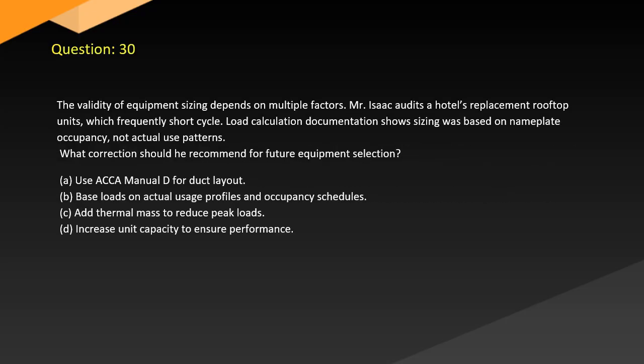Question 30. The validity of equipment sizing depends on multiple factors. Mr. Isaac audits a hotel's replacement rooftop unit, which frequently short cycles. Load calculation documentation shows sizing was based on nameplate occupancy, not actual use patterns. What corrections should he recommend for future equipment selection? A. Use ACCA Manual D for duct layout. B. Base loads on actual usage profiles and occupancy schedules. C. Add thermal mass to reduce peak loads. D. Increase unit capacity to ensure performance.